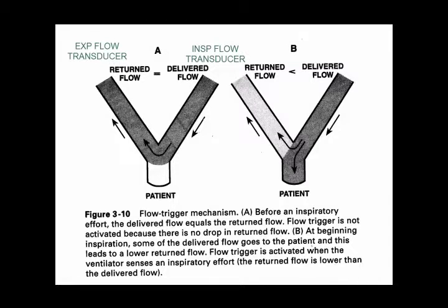Go ahead, Holly. Going beyond the trigger, but when it's triggering to give a breath, is it trying to compensate for the lack of breath that's coming back? No. It just recognizes that the patient wants something and it's turning the ventilator on to begin the inspiratory phase. Remember, this is the transition from exhalation to inhalation. Something's got to turn it on. And at this point it says, oh, I see some flow has been gone. That must mean a patient wants some. Here's the breath.